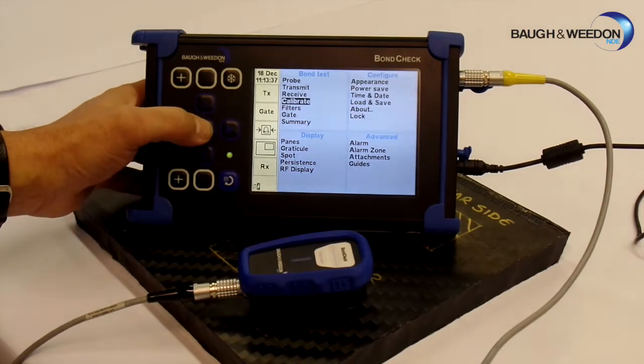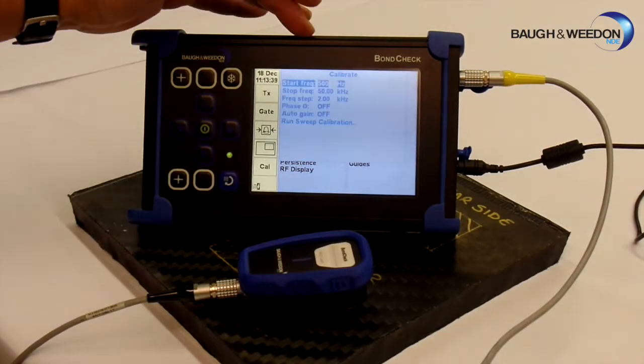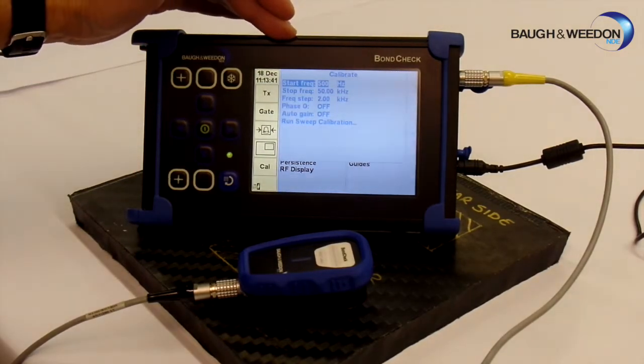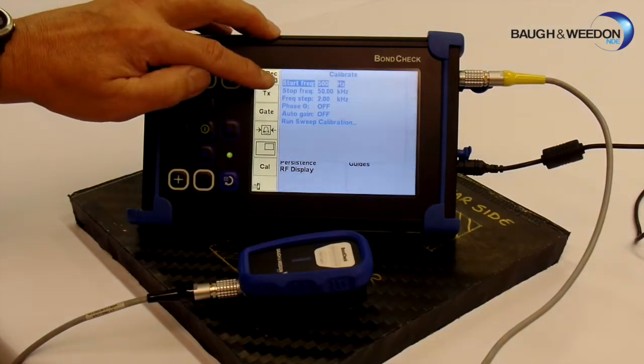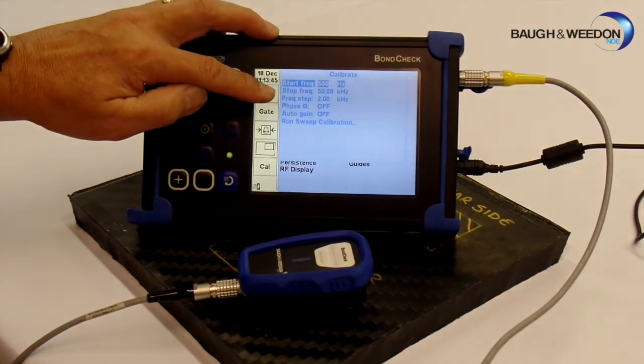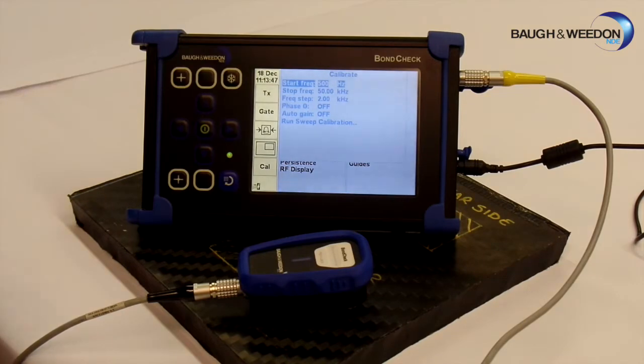We can now go down to calibrate, select calibrate. This unit has a frequency range that starts at 500 Hz and it goes up to 50 kHz. If we knew, or we are looking at an inspection that had already been written for another type of unit, we could adjust this so that we sweep over a smaller area.